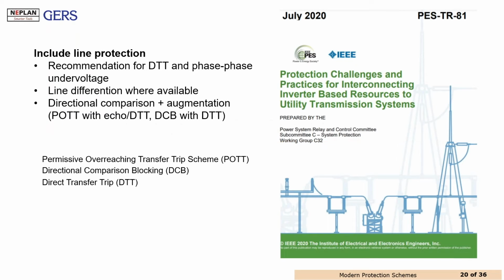I'm going to start here by presenting some recent publications. For example, this publication is from the IEEE committee, presenting the protection challenges and some methodologies for the protection of transmission systems with high penetrations of inverter-based resources. And we can see how these publications recommend direct transfer trip, permissive overreaching transfer trip schemes, or directional comparison blocking. Some of them are based on communications, because when we have the opportunity to communicate the relays, some of them can block the operation of any other remote relay.